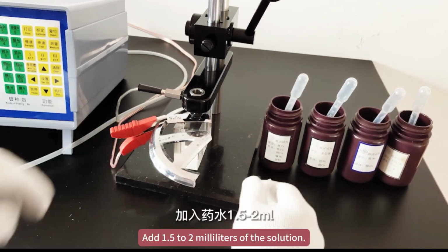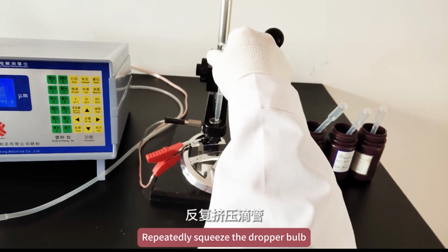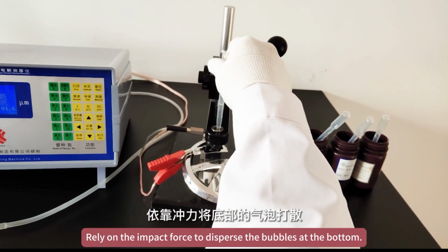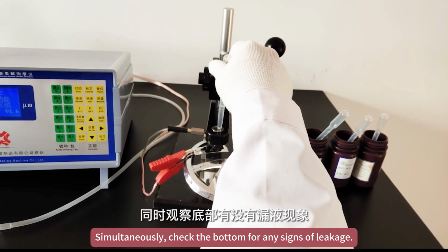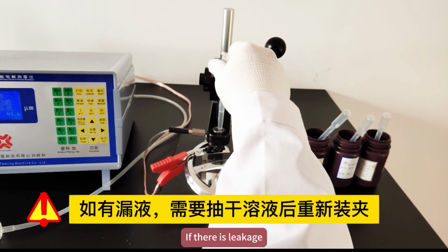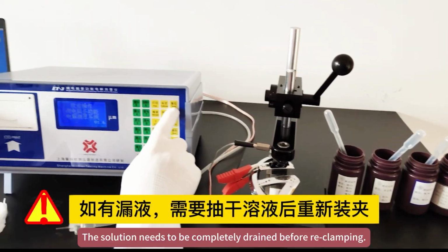Attach the anode clip. Add 1.5 to 2 milliliters of the solution. Repeatedly squeeze the dropper bulb. Rely on the impact force to disperse the bubbles at the bottom. No bubbles should form at the bottom of the beaker. Simultaneously, check the bottom for any signs of leakage. If there is leakage, the solution needs to be completely drained before reclamping.